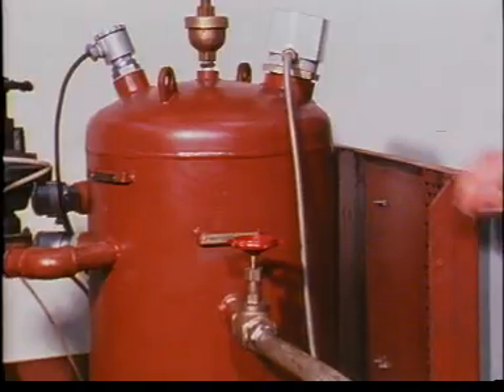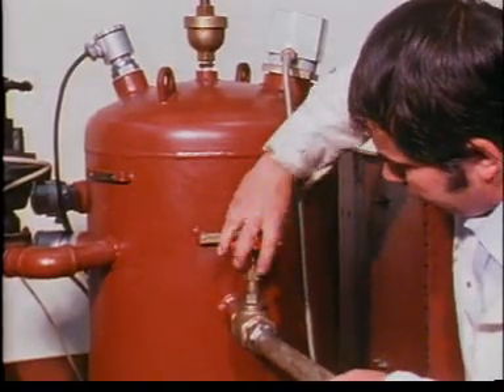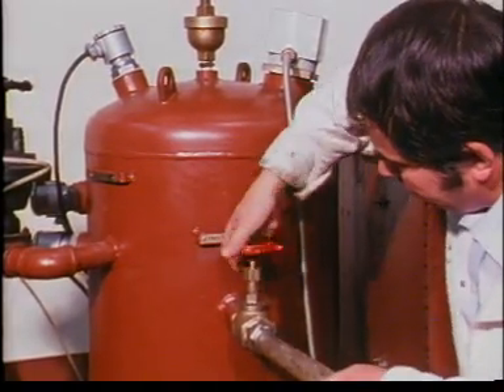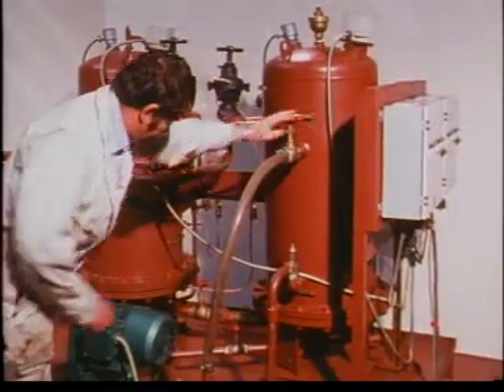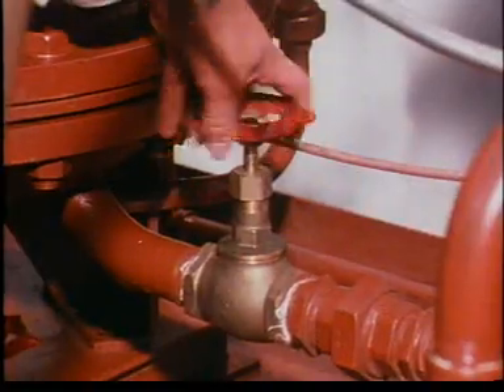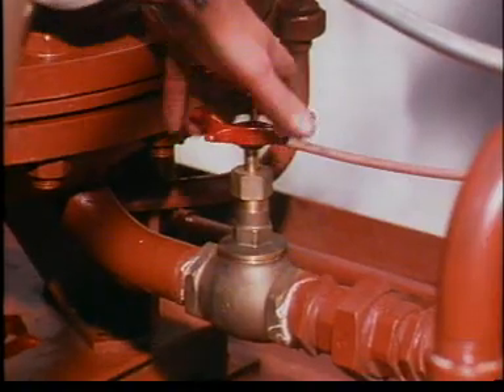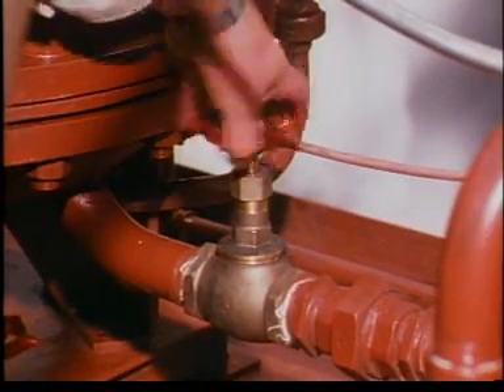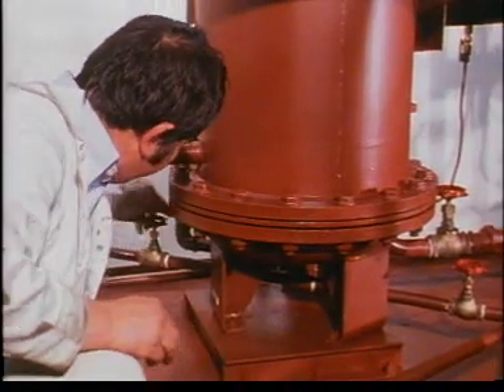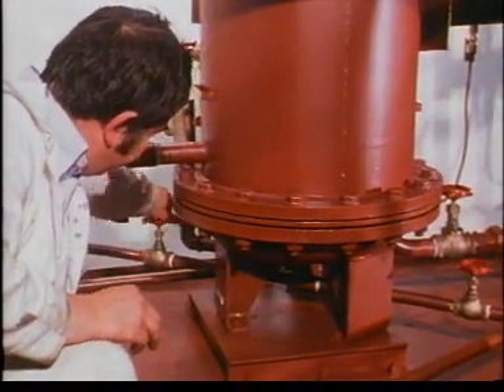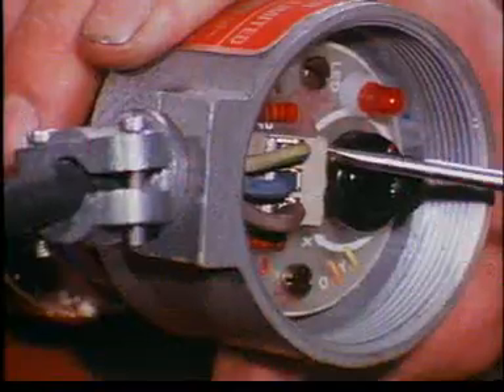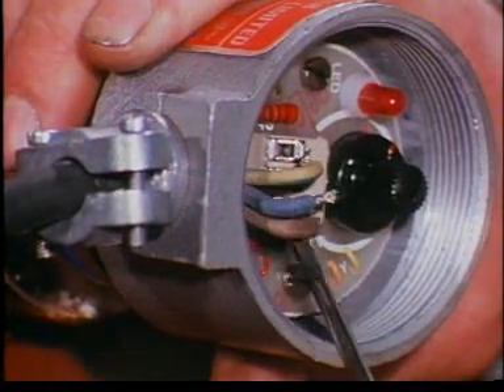When the whole system has been cleaned internally and is full of clean water, the mixture inlet valve on stage 1 is closed. Then the isolating valve on stage 2 is also closed, and also the shipside valve. The stage 2 drain valve is now opened and the coalescer is drained. We now prepare to remove the coalescer dome.